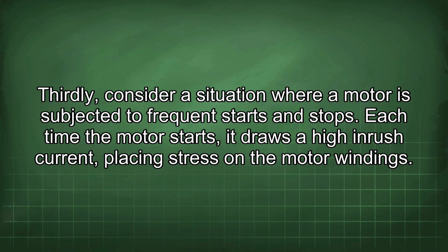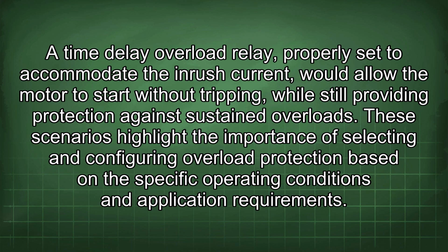Thirdly, consider a situation where a motor is subjected to frequent starts and stops. Each time the motor starts, it draws a high inrush current, placing stress on the motor windings. A time delay overload relay properly set to accommodate the inrush current would allow the motor to start without tripping while still providing protection against sustained overloads.